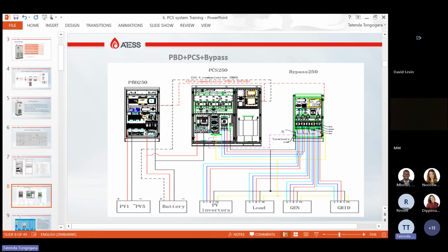So this is our PBD, your PCS, your bypass. On the PBD, there is no limit to the number of PBDs that you can have on your system. You can have as many as you want. I think the only thing that can limit the number of PBDs is the size of your battery and your PV size. So on the PCS, I said 4. On the bypass, you can have your bypass 500, you can have your bypass 1000, doesn't matter. But here you have your PCS 250, and your 1000 here, you can have 4 of these connected to one bypass 1000, or 2 of these connected to bypass 500.